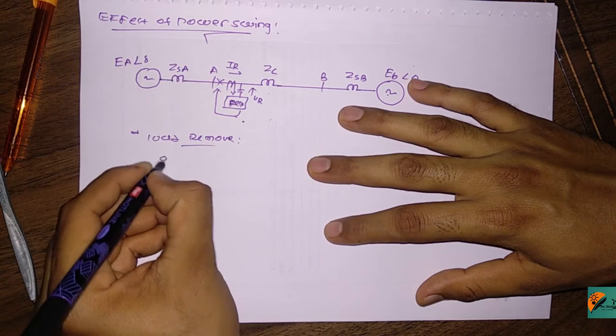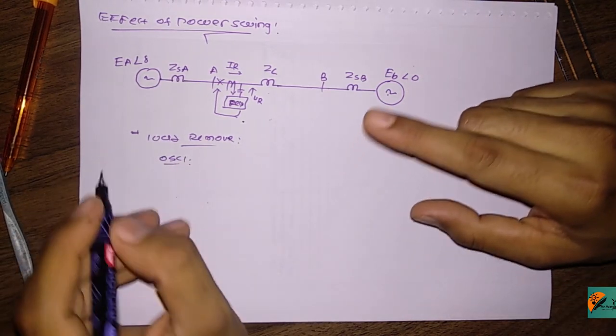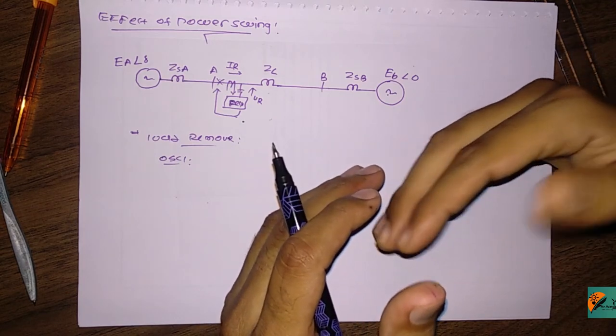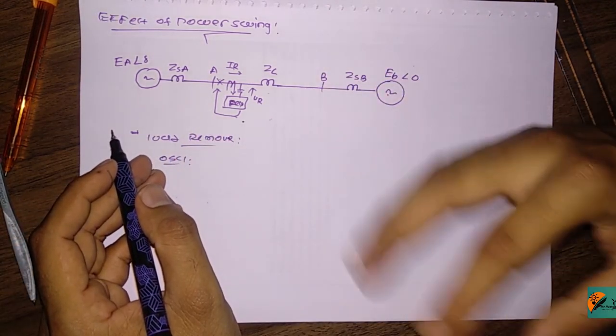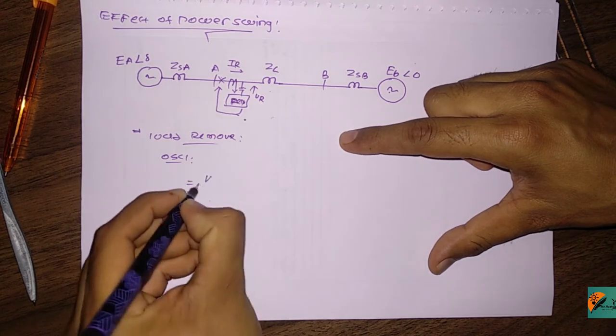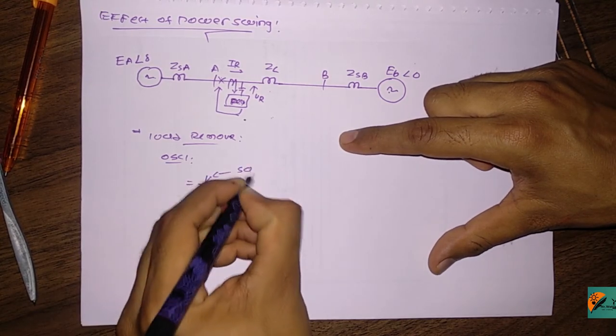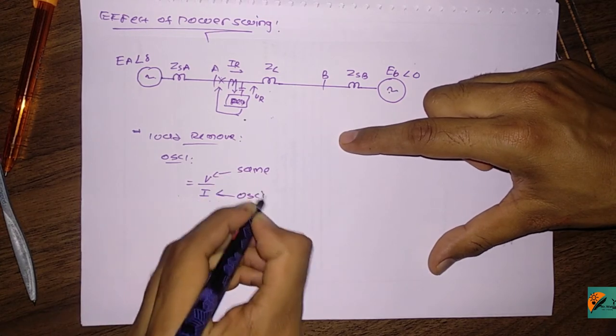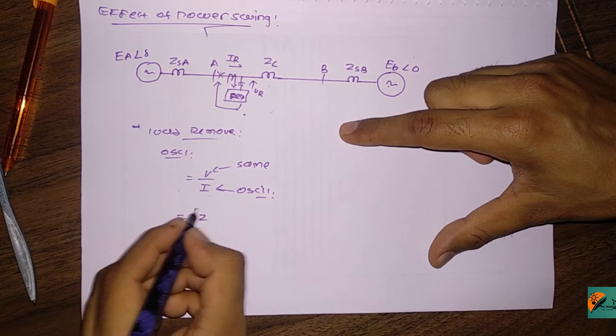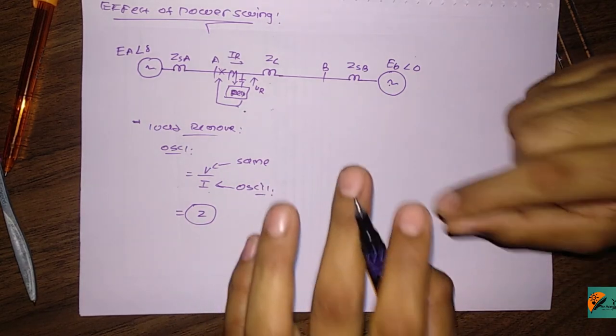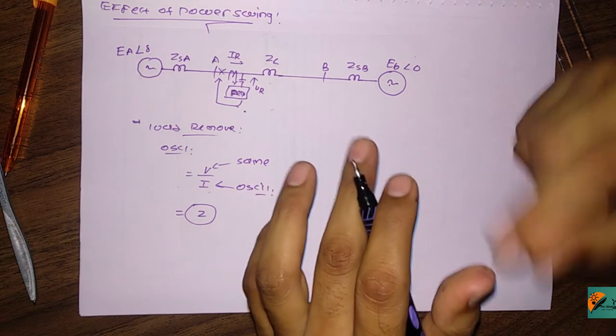The effect of power swing: the system starts to oscillate. Your rotor angle starts to oscillate - the rotor angle keeps oscillating. If the rotor oscillates, then a huge value of current passes for some time, which can also affect your rotor winding. V remains the same but I oscillates. That means V divided by I equals Z, so this Z becomes less than the actual value of the impedance.